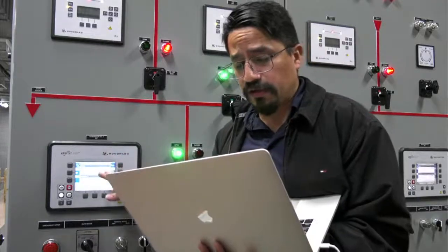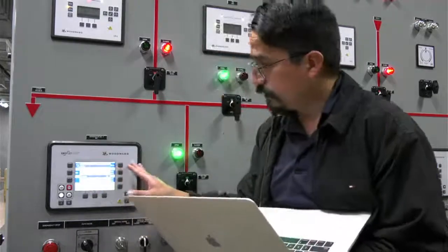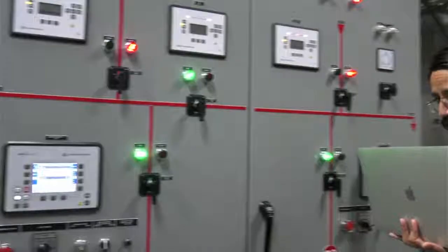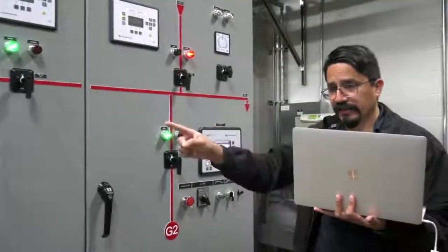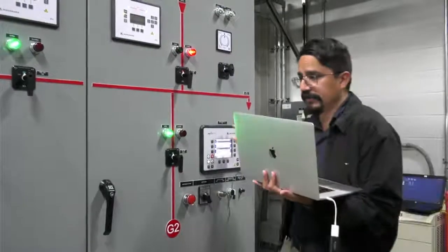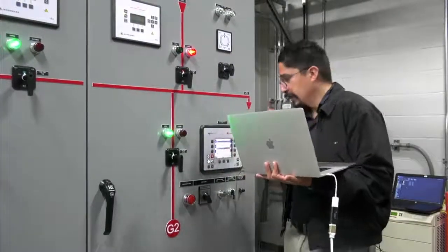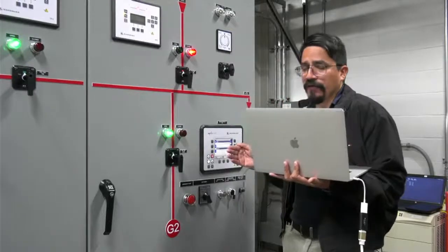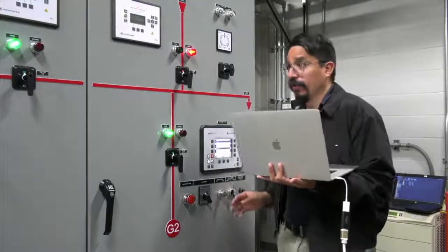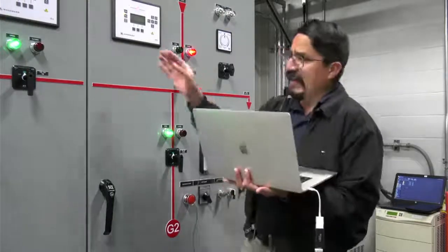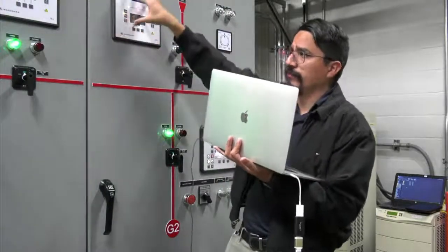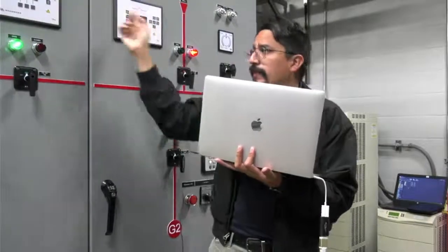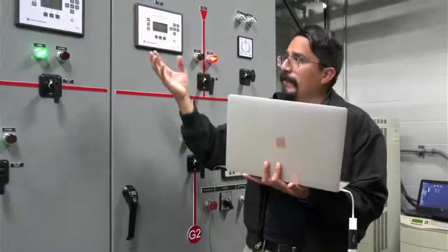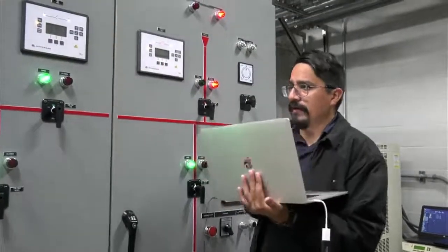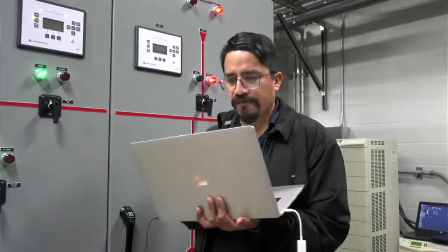The main programming resides in these 2 controllers. It's the same control, right? The same model, but you cannot swap it. You cannot interchange the EasyGen because each EasyGen knows where it is, so the software has to be different from one to the other. The same happens with the LS5s. You cannot replace them and swap them, because even though the model is the same, each LS5 is programmed in a different way.